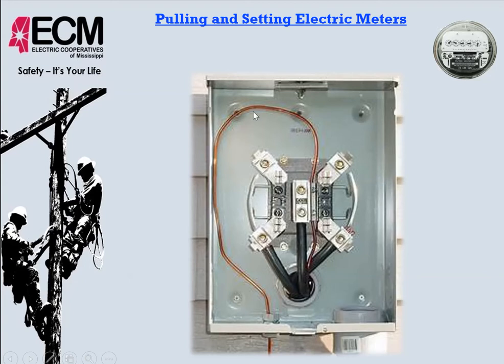If you're going to come over the top like this, it needs to be insulated. Really and truly, there's no need for this one going inside. If there is a need for an appliance ground to come from the meter base, this would need to be double lug, come off the bottom, needs to be insulated to run in this conduit with other insulated cables.